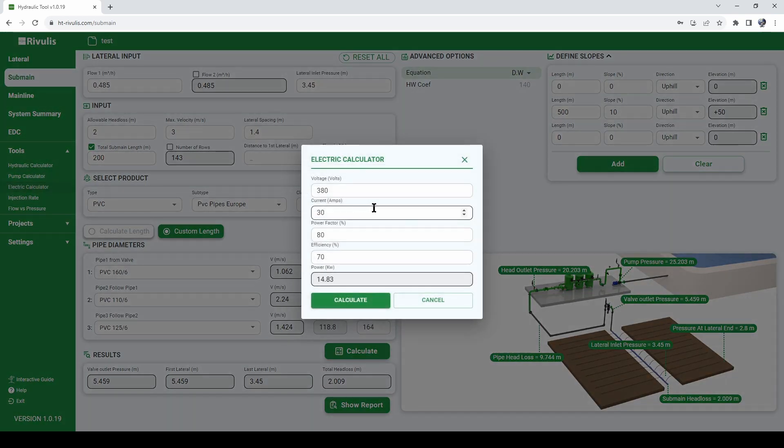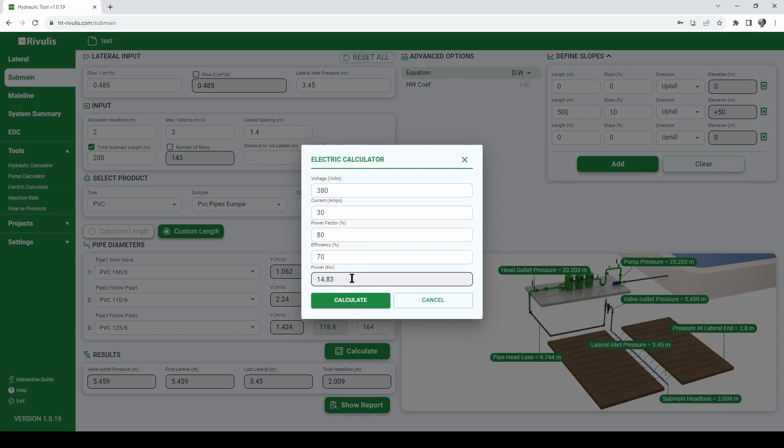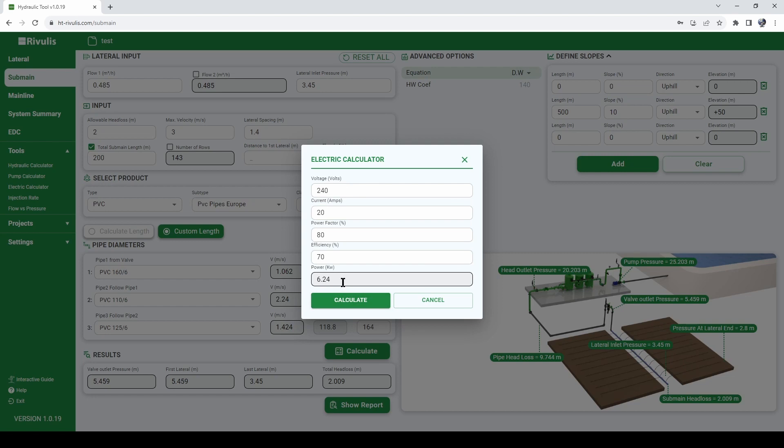The next tool is an electric calculator. Again, to calculate the power requirements given the voltage, amperes, and other electric coefficients. So let's say we have 240 volts, 20 amps, let's keep the same power factor and efficiency, click calculate. So we need a 6.24 kilowatt pump.